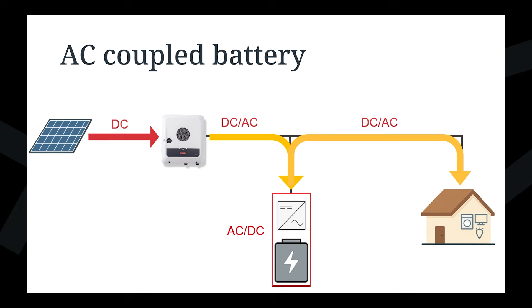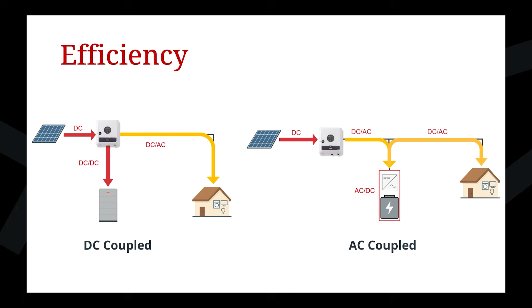So in terms of benefits of having a DC coupled battery, one of the ones that you might have been able to pick up on is efficiency. Okay, so with a DC coupled battery, you essentially have one conversion, right? So going in as DC, and then it gets converted to AC to go to your loads. With the AC coupled battery, it's getting converted from DC to AC, right? It goes in and then gets converted again to be stored as DC, and then it gets converted again to go out as AC power, all right? And with each conversion, there are losses. So DC coupled batteries use your solar power more efficiently. And over time, that can mean quite a bit in terms of savings, in terms of energy, and then associated savings in terms of financial benefits as well.